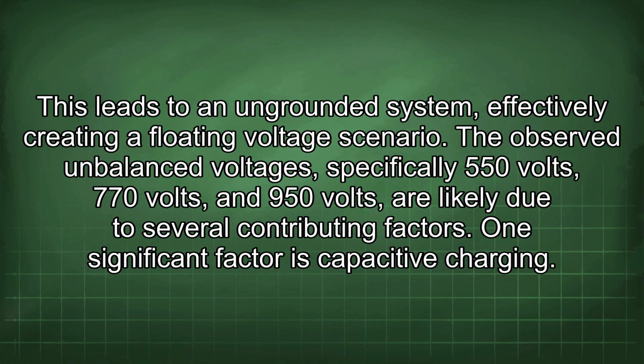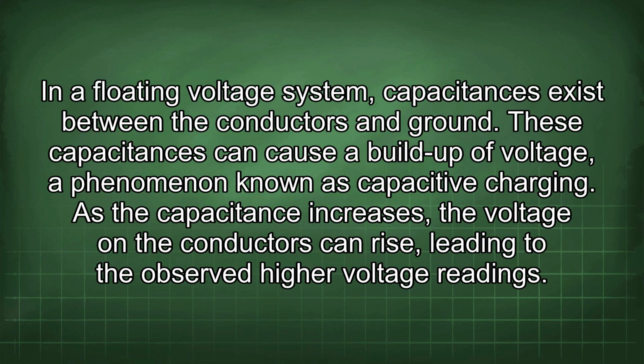The observed unbalanced voltages, specifically 550 volts, 770 volts, and 950 volts, are likely due to several contributing factors. One significant factor is capacitive charging. In a floating voltage system, capacitances exist between the conductors and ground. These capacitances can cause a buildup of voltage, a phenomenon known as capacitive charging. As the capacitance increases, the voltage in the conductors can rise, leading to the observed higher voltage readings.